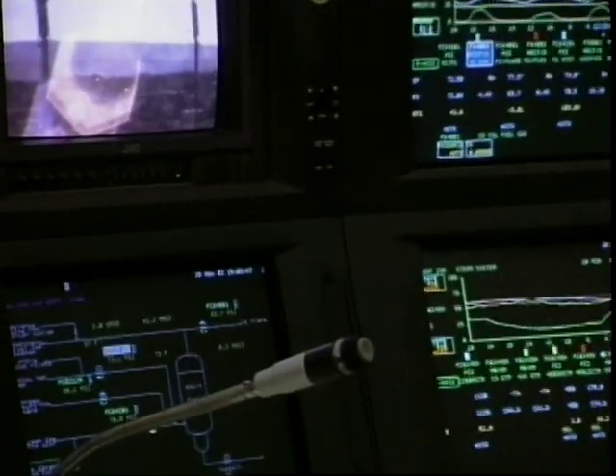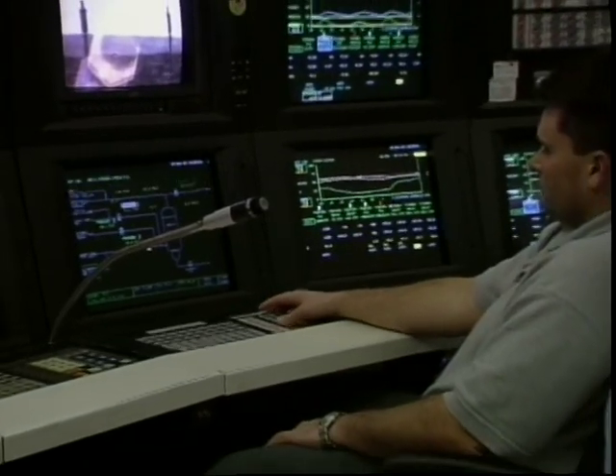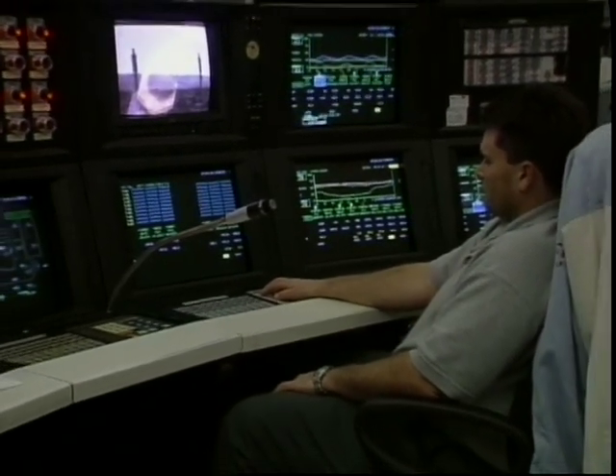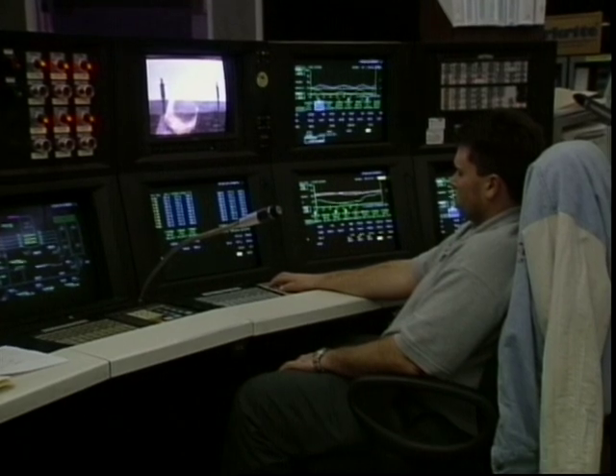What is the black smoke? Occasionally, black smoke is emitted from the flare system when there's a lack of steam to aid in the combustion for the flares. Refinery personnel are constantly watching the flare system via television monitors so that steam flowing to the flares can be adjusted as needed. In the rare instance of a sudden release of hydrocarbons to the system, there may be a delay in getting steam to the flare system. Therefore, black smoke may be emitted from the flare stacks.